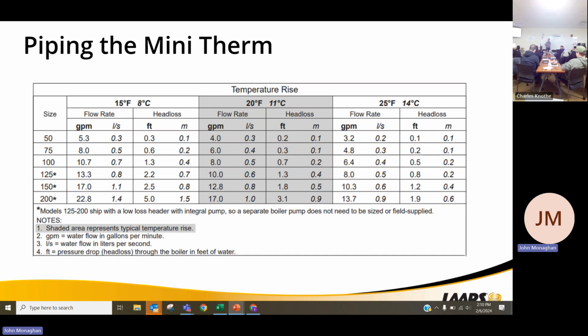All of our larger products, 125, 150, and 200, are going to come with that low loss header on there. You would just put whatever system pump you need on the outside to move the water around. That's going to guarantee that unit gets its proper flow.